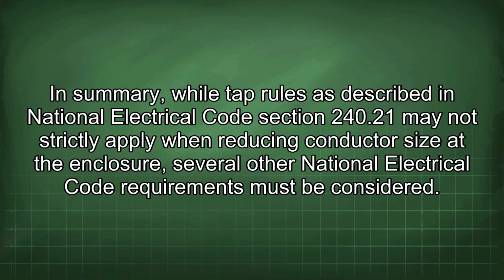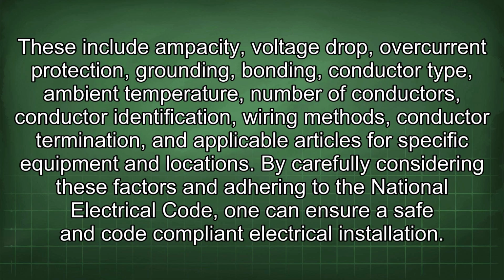In summary, while tap rules as described in National Electrical Code Section 240.21 may not strictly apply when reducing conductor size at the enclosure, several other National Electrical Code requirements must be considered. These include ampacity, voltage drop, overcurrent protection, grounding, bonding, conductor type, ambient temperature, number of conductors, conductor identification, wiring methods, conductor termination, and applicable articles for specific equipment and locations. By carefully considering these factors and adhering to the National Electrical Code, one can ensure a safe and code-compliant electrical installation.